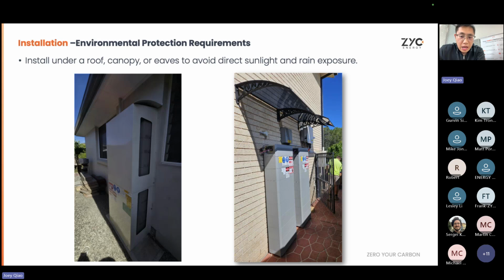The battery is IP65 rated, so you can put it indoor or outdoor. As you can see in the pictures, on the left and right hand side, always make sure there's no direct sunlight. On the left hand side, they put our battery in an enclosure cover, which is actually a pretty good solution. On the right one, they put a rain cover to make sure there's no direct sunlight or direct rainfall. That's pretty important for us.